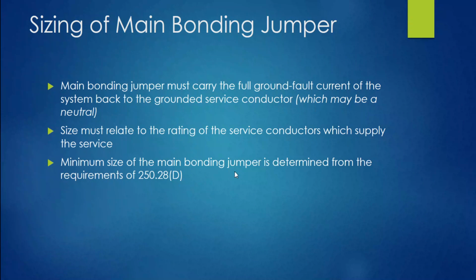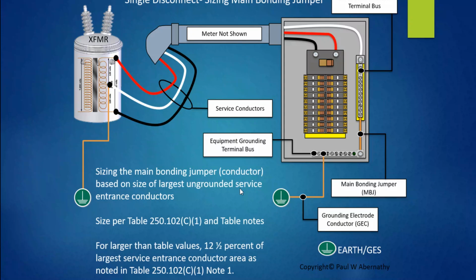All right, now sizing that main bonding jumper, let's get into that. The main bonding jumper must carry the full ground fault current of the system back to the grounded service conductor, which may be the neutral. You always have a grounded conductor, but you might have a neutral, depending on the system. If you're residential, most all the time you're going to have a grounded AC system. Now, size must relate to the rating of the service conductors which supply the service. Remember that. We're sizing this main bonding jumper based on the service conductors supplying the service. The minimum size of the main bonding jumper is determined from the requirements of 250.28(D), which ultimately sends us to 250.102(C)(1).